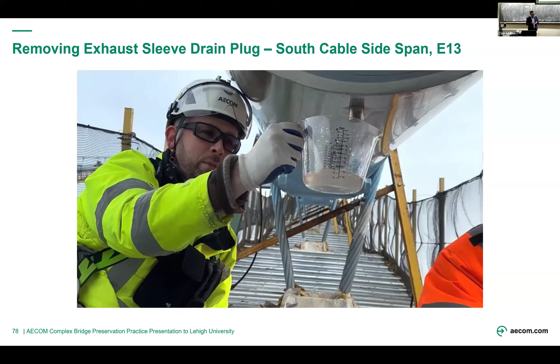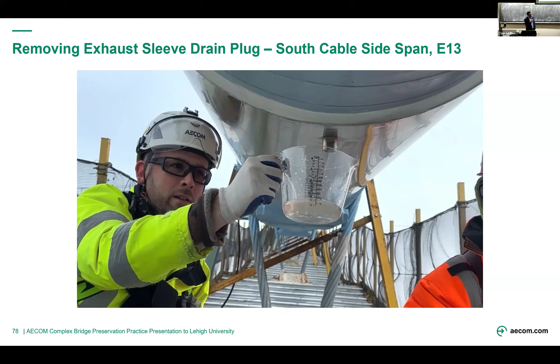Every once in a while during this period - maybe the first year on a normal bridge, or the first couple to three years on this bridge - during biannual inspections, you can go out and pull these drain plugs if the relative humidity level is high in these spots. That will accelerate the drying out of the bridge and the cable.